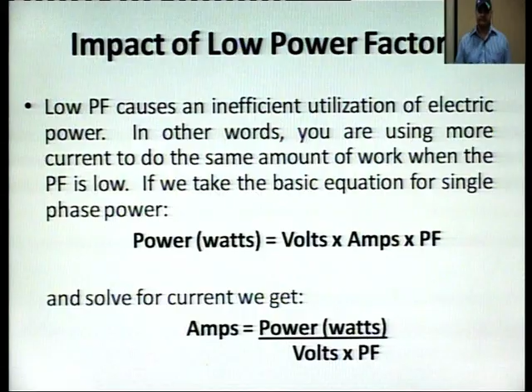So this is an example of how low power factor affects the current. We have 100 kilowatts of real power and 100 kVAR, and then the kVA becomes 141 kVA. So the cos phi is 100 divided by 141, that is 70%, or a power factor of 0.7. Now we again have 100 kilowatts of real power, but the reactive power is 32 kVAR instead of 100 kVAR.